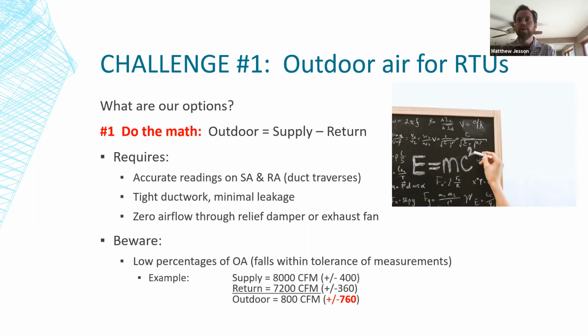One thing to watch out for, even if you do have good duct traverses and all the conditions are right for using this method, one problem that you might run into is if you have a really low percentage of outdoor air, it could actually fall within the tolerance of the measurements. So even a good duct traverse has some uncertainty. The accuracy is limited on TAB instrumentation. So let's say you got a supply reading of 8,000 CFM, that could be plus or minus 400. A return, 7,200, could be plus or minus 360.